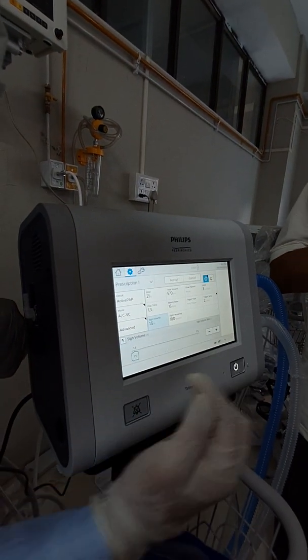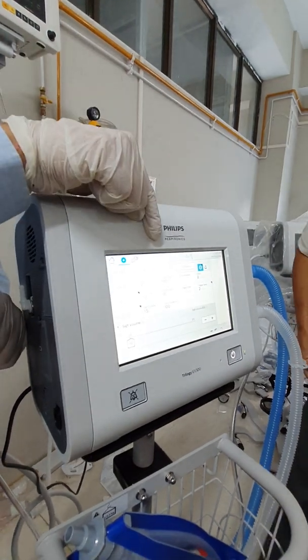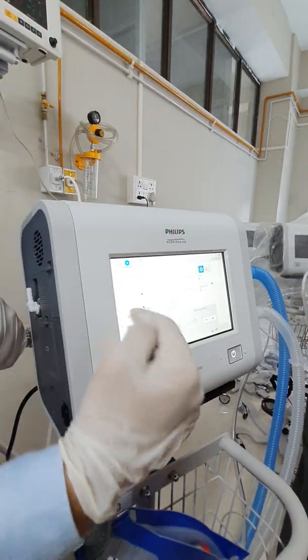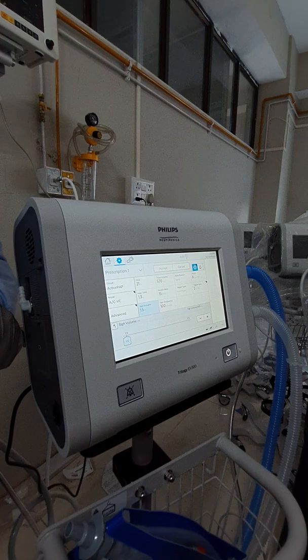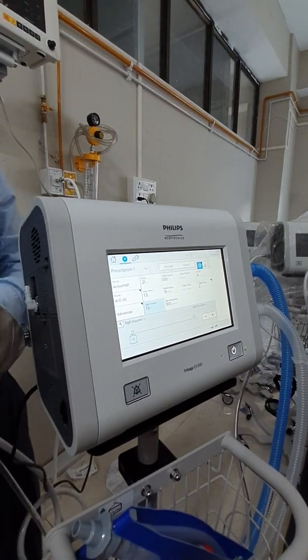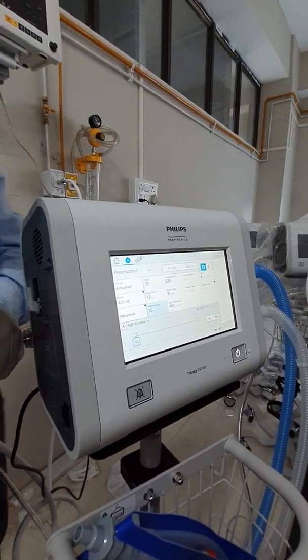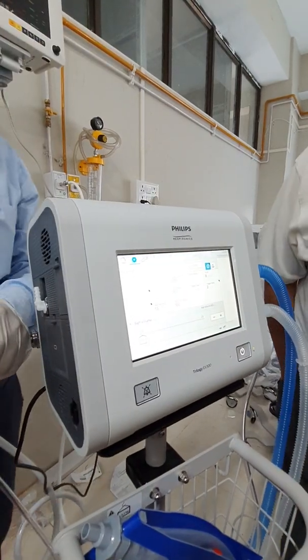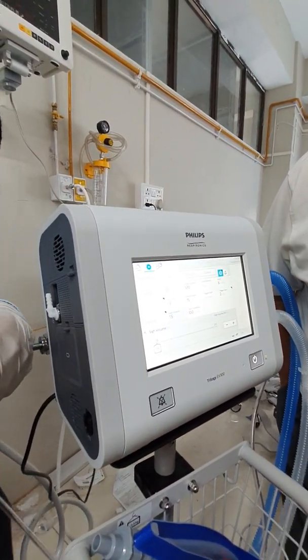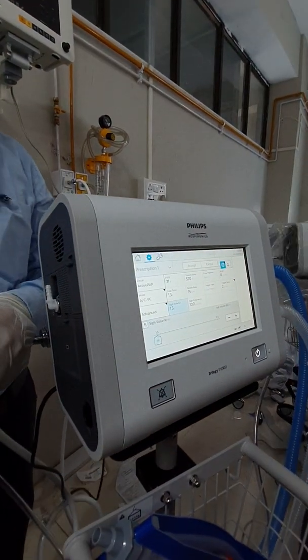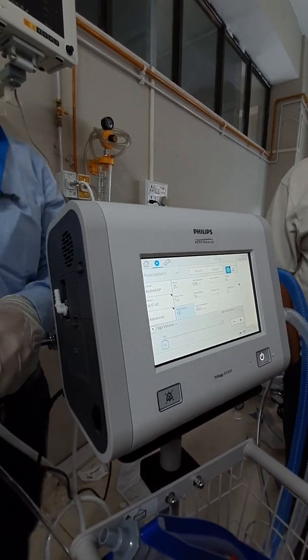Now what you do: if you select a sigh volume of 1.5, that means if 570 is my set tidal volume, it will be 1.5 times this. Only one breath will rise, and then it goes back. You can also set the sigh frequency, meaning after how many breaths you want that volume. That you can set. It's just like a recruitment method.